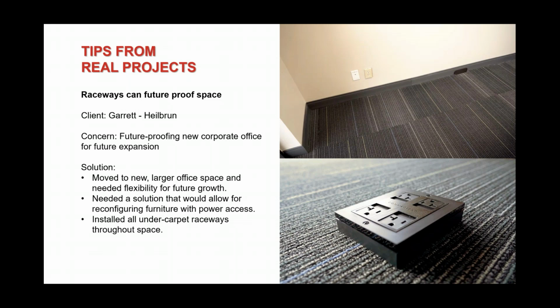Okay, if you need this installed, your facility team often, again depending on the size of your company, can install everything because it's very simple to install. You will need a licensed electrician to bring the power in. That part where we talked about at the wall, where you're going up to a junction box or something like that, will require an electrician. From that point on, it does not require an electrician.